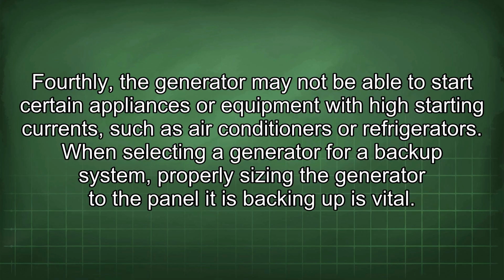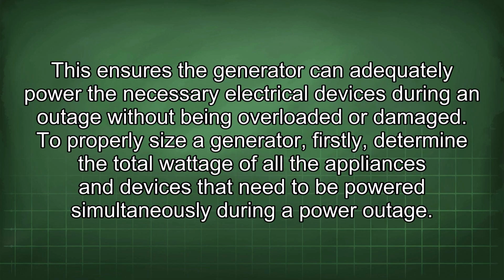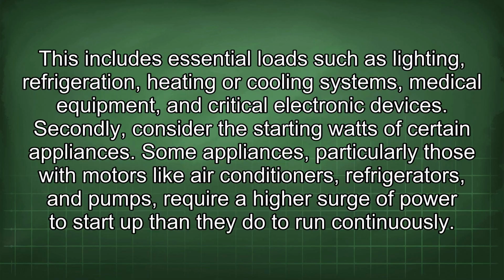When selecting a generator for a backup system, properly sizing the generator to the panel it is backing up is vital. This ensures the generator can adequately power the necessary electrical devices during an outage without being overloaded or damaged. To properly size a generator, firstly determine the total wattage of all of the appliances and devices that need to be powered simultaneously during a power outage. This includes essential loads such as lighting, refrigeration, heating or cooling systems, medical equipment, and critical electronic devices.